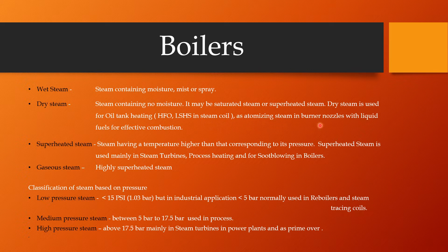Dry steam is also used as atomizing steam in the burner nozzle, in which the liquid fuel is used for efficient combustion. If you use superheated steam in place of dry saturated steam, thermal cracking will occur. Instead of oil firing, it will lead to gas firing and further explosion in the burner tip itself. So we have to use dry saturated steam for steam atomization in the burner nozzle, where liquid fuel is used as fuel.